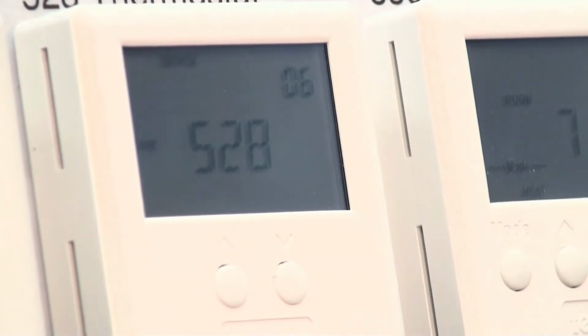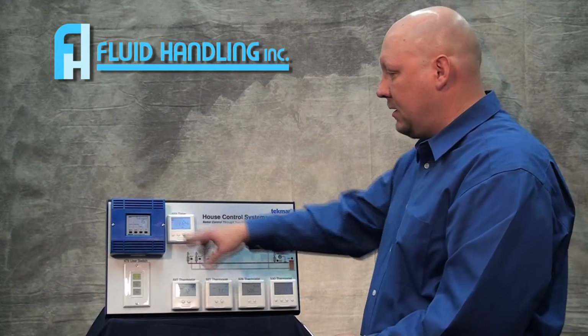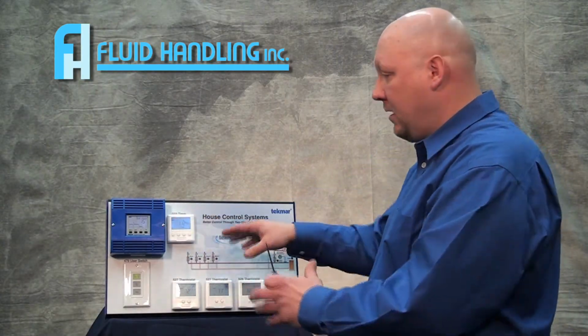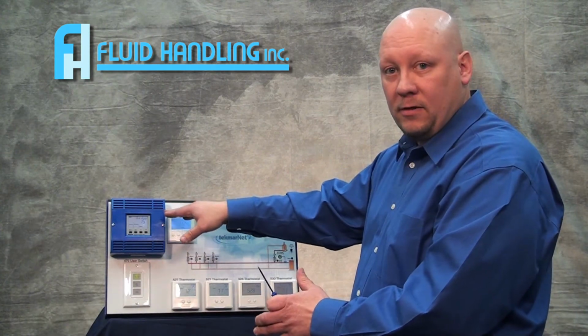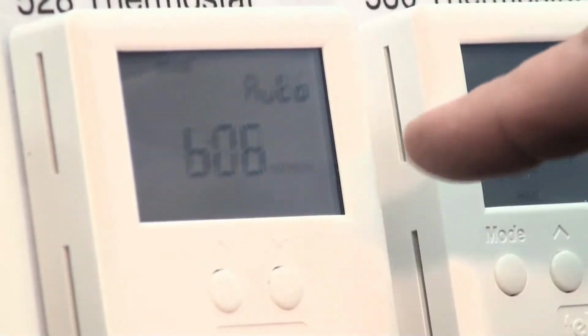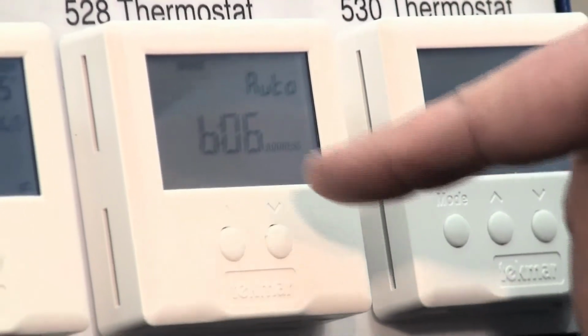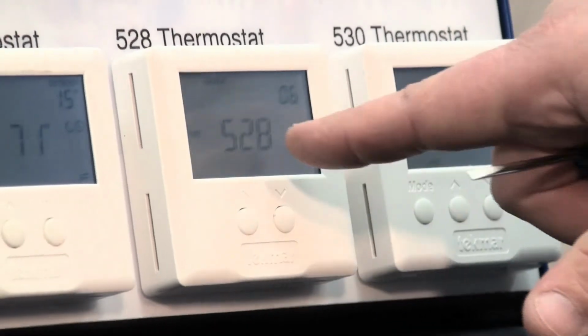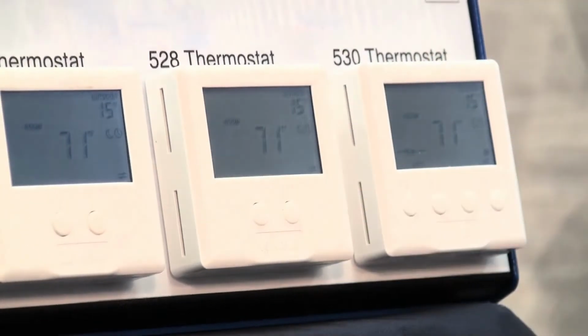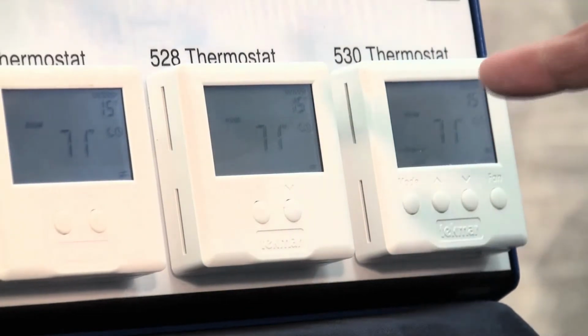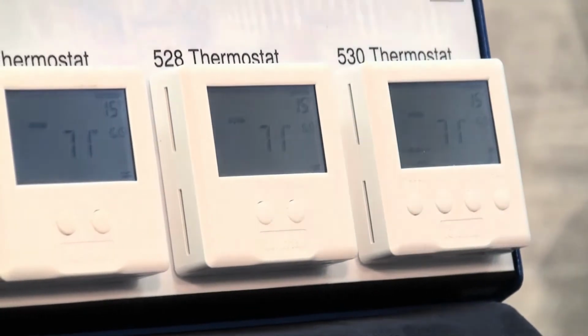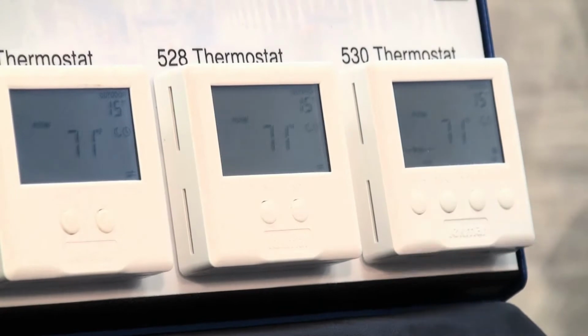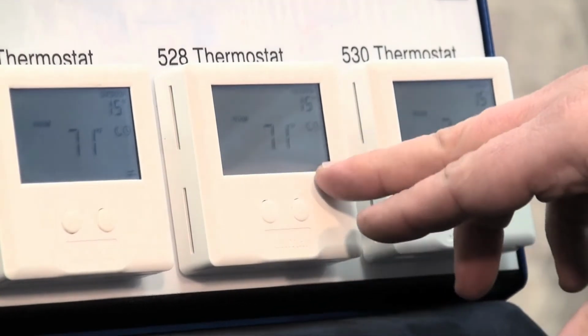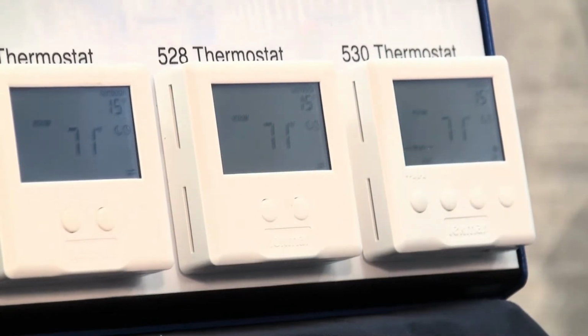And now we're back to, this is device number 06. So up here on my bus, if it showed me that device lost as 606, this is my thermostat that went missing. And then it's showing the current, it's a 528 and it's 06. And you saw it flash where it was showing auto. It was just auto addressing itself to the control, and it stayed on 06. And again, we've got our 2 arrows. That's telling us it's communicating.